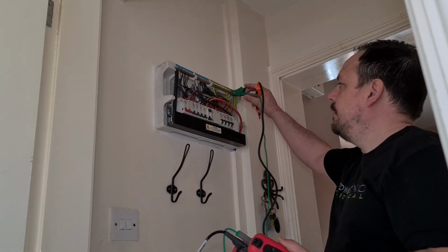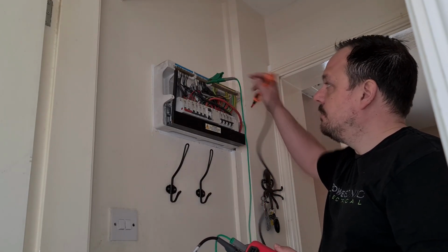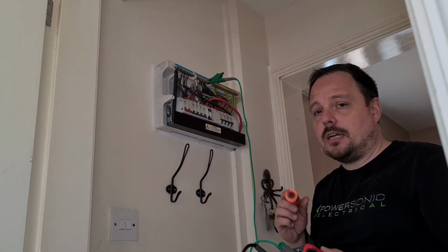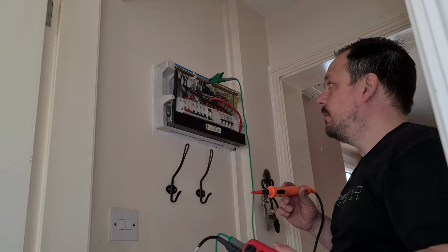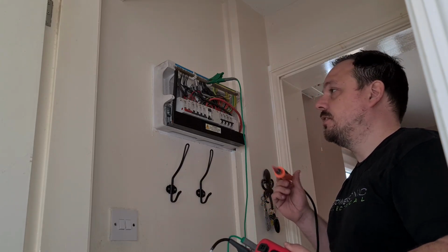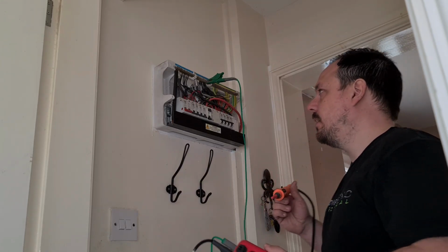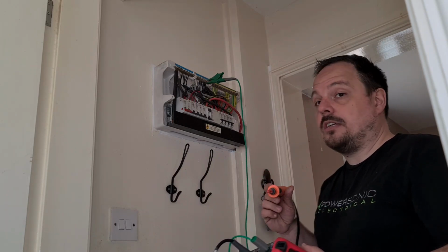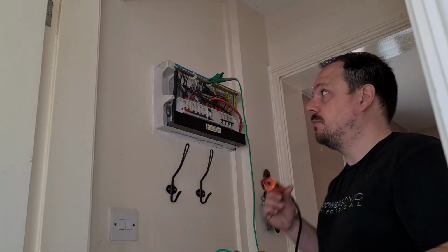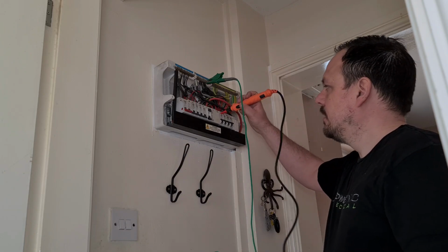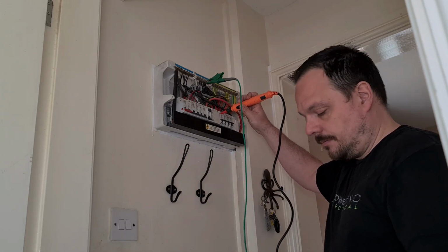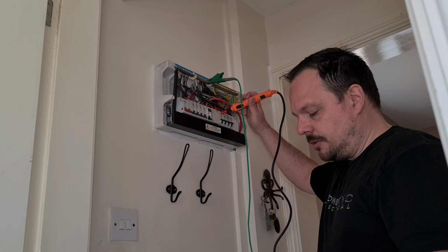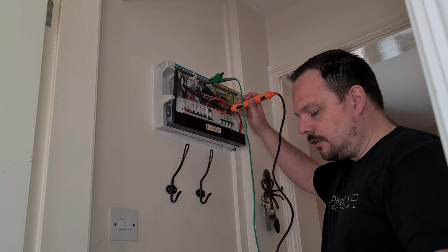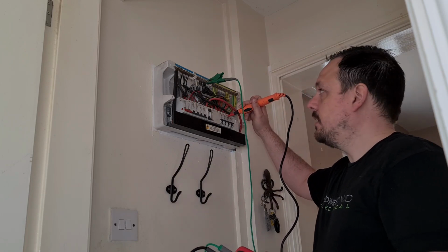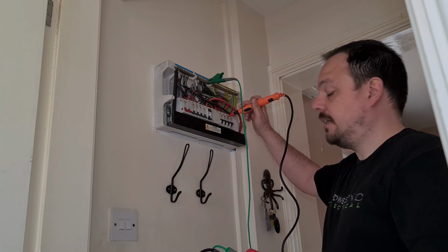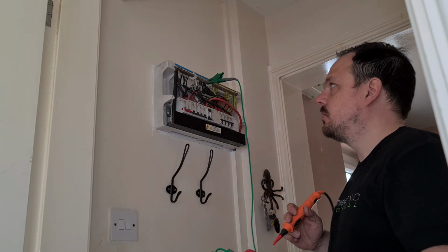And then equally, if you wish, you can then take a measurement between the line and neutral. Now with this one, you need to be careful if you have any equipment connected in circuit. This is where the readings will start to go a bit haywire. And again, I would always encourage starting at 250 volts before you go straight to the 500. Then again, you can take a measurement. And so again, between the neutral and the lines, we've got over 500 megohms.